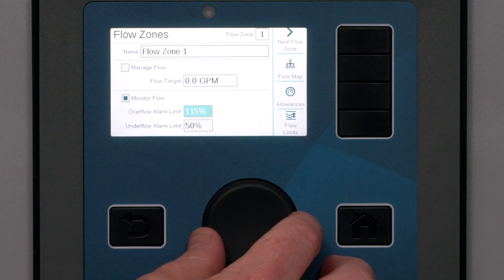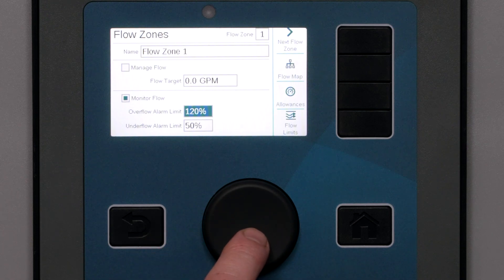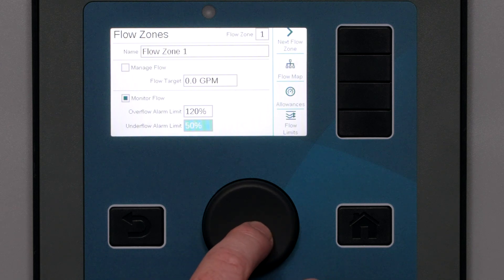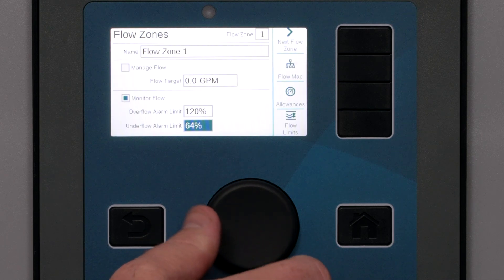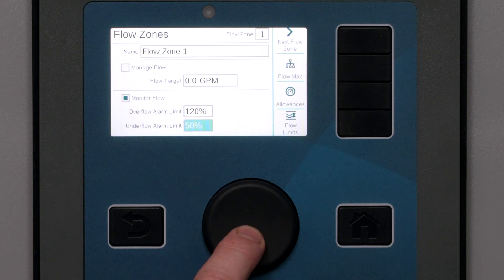City water pressures vary at certain times of the day, and pump operations can also cause the flow rate to surge or drop. Set the overflow limit to allow for normal variations but still be able to catch real malfunctions in the field. For this example, we'll set the overflow to 120%. This means that if normal flow should be 20 GPM or 75 LPM, the system will not alarm until flow exceeds 24 GPM or 90 LPM. Similarly, an underflow setting of 50% with a normal flow of 20 GPM would mean diagnostics begin at 10 GPM or 38 LPM. For now, we'll leave this at 50%.